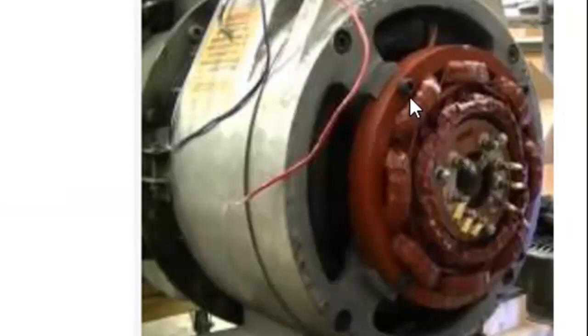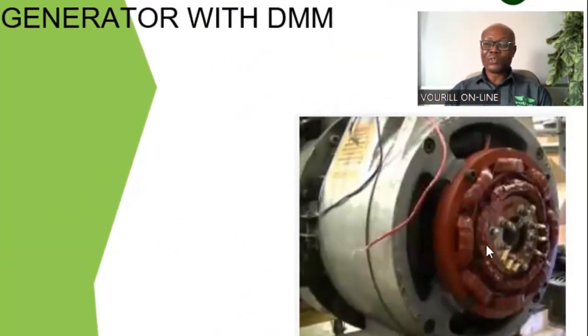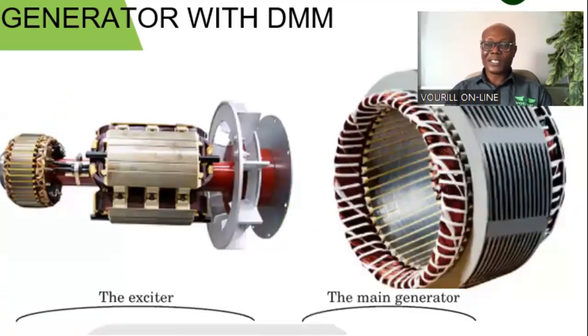So the wires, the output from the AVR, which is this two from the positive red and negative black from the AVR, is fed to the exciter field. So that helps to magnetize the exciter field. That magnetism will now induce voltage into the rotating exciter armature for us to have the voltage, okay, that will be sent to the rectifier bridge or to the diode plate that will now be rectified and sent to the main field to magnetize the main field. So that is how we have the exciter armature, exciter field, I mean to say.